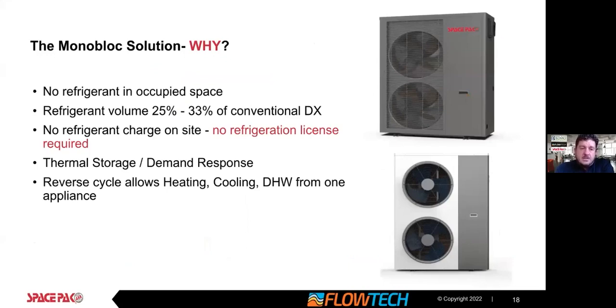Starting on monoblocks. Why do we love monoblocks? There's many reasons, and Albert touched on a few which are repeated here. No refrigerant in the occupied space. Overall, greatly reduced refrigerant in the system. There's another component to this too, which is human health and comfort. When refrigerant leaks inside the occupied space, there's an element there of safety issue for folks.